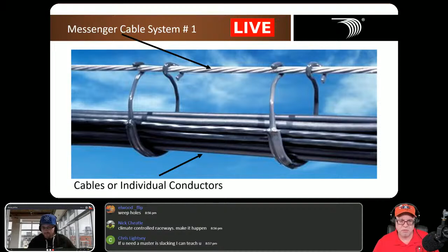And this is an example of a messenger, and this is individual conductors, but it could have just as easily been MC PVC jacketed on it as well. But this kind of gives you an idea. A messenger is a supporting system from point A to point B. It's secured at each end. It could be from building to building, from building to structure, from building to pole. Okay? All of those applications, that's what a messenger does, and it's allowed to support individual cables or individual conductors as well in a messenger. All listed in 396.10. You'll have a list of different things that can be supported from a messenger.